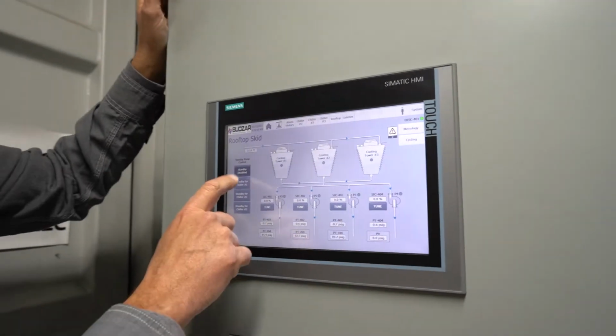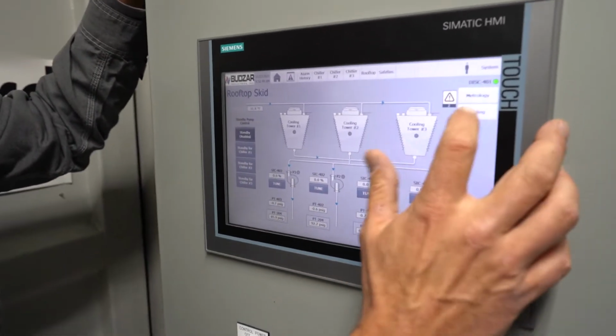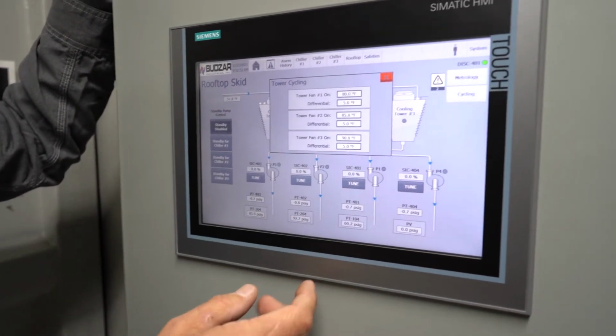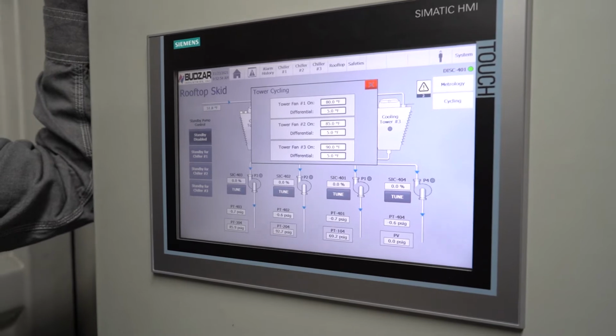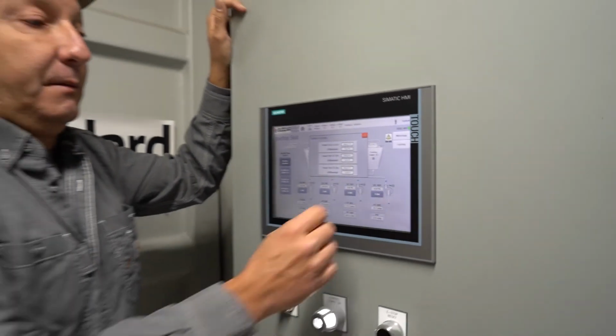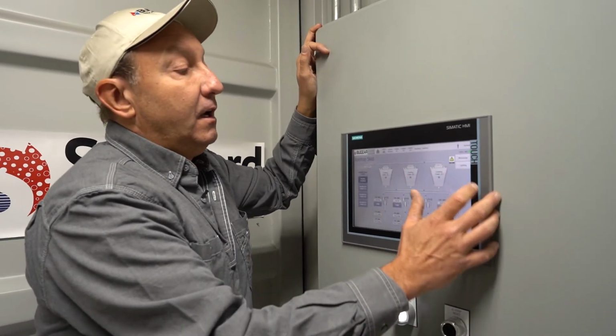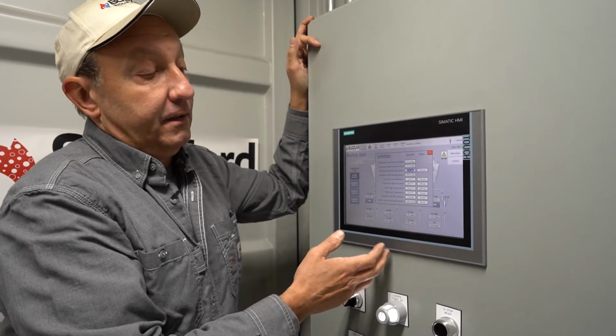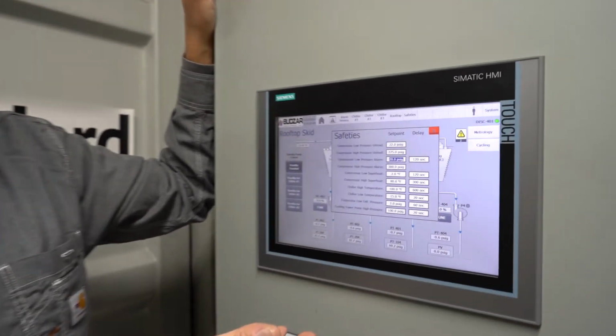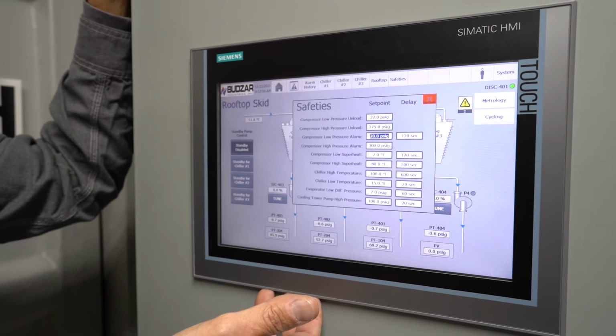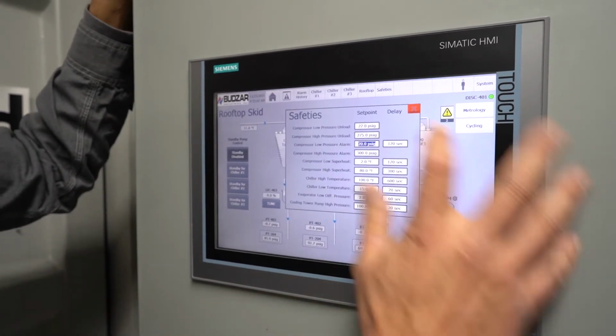On this screen, you could select each tower, and we also have a cycling parameters. This is what controls when the fans cycle on and off, at which temperatures they come on and off. We have a safety screen. This is all of our program safeties. These are also noted on our schematics for reference, but they're also saved here.